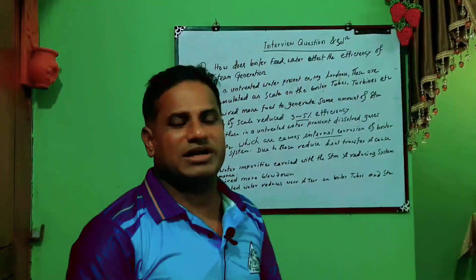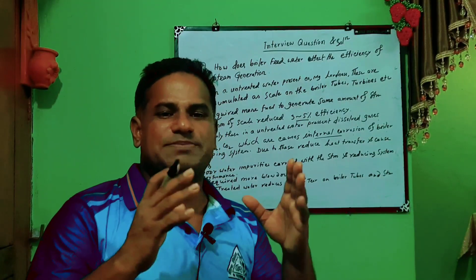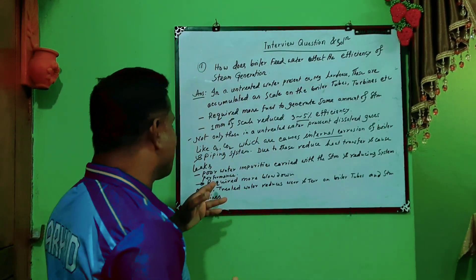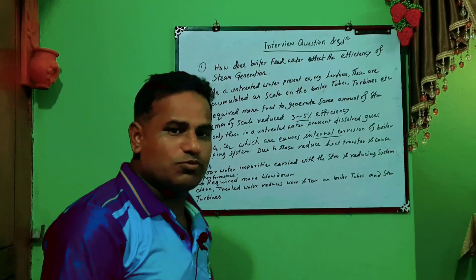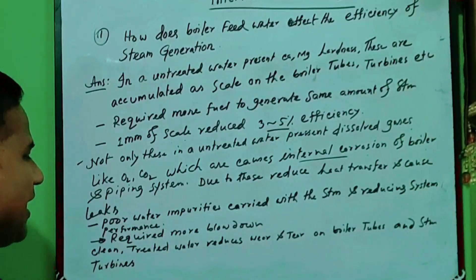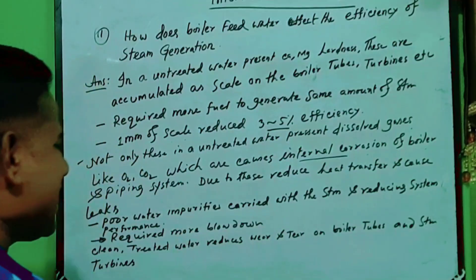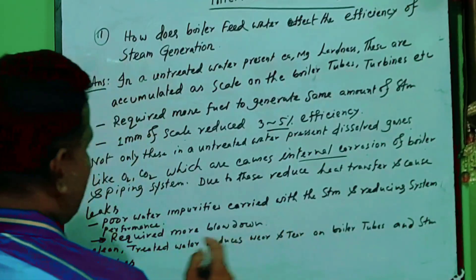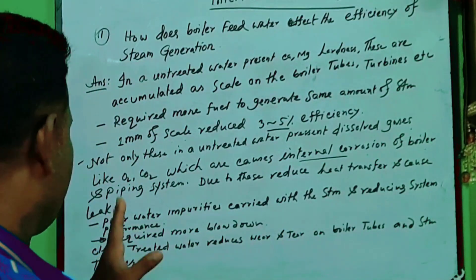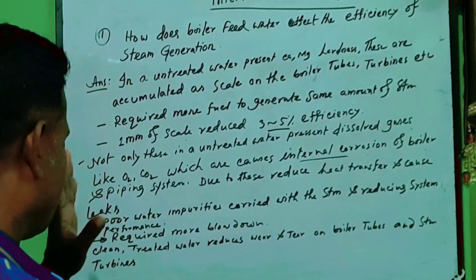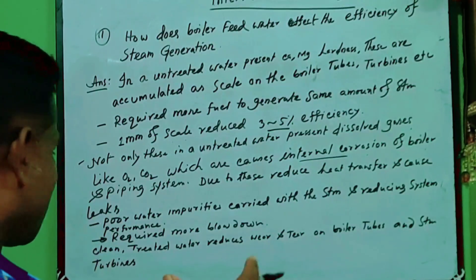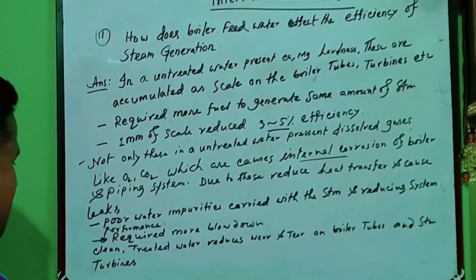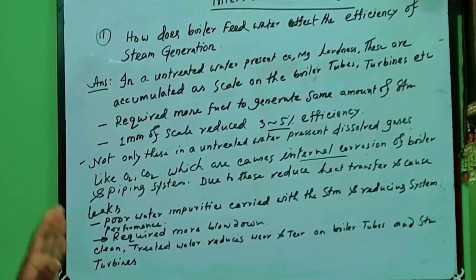Additionally, more blowdown is required when untreated water is used, because the pH and hardness levels increase and must be controlled. When more blowdown is performed, both water and energy are lost.